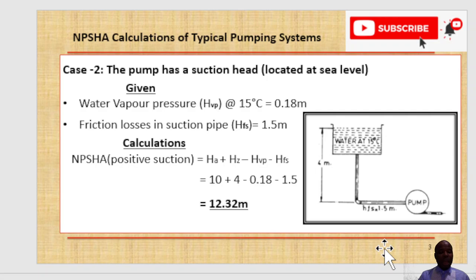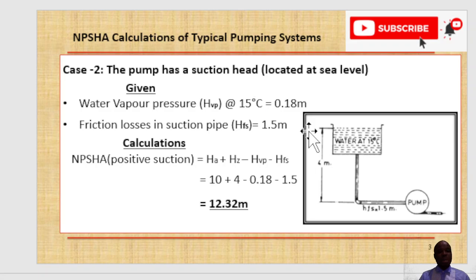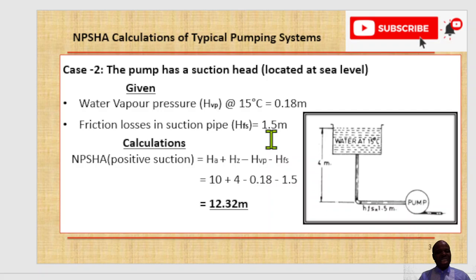For Case 2 the process fluid is again water, and the pumping temperature is 15°C. The vapor pressure at this pumping temperature is given as 0.18 meter. If your vapor pressure is in kg/cm², you need to convert it to meters using specific gravity — refer to the previously uploaded sessions on NPSHA for that conversion. Friction losses in the suction pipe are given as 1.5 meters.